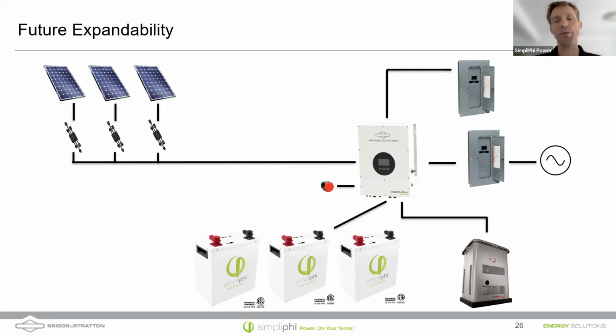The other nice thing about having that generator is generators typically operate at their highest efficiency when they're mostly loaded. So around 90% load, the generator is producing energy most efficiently from the fuel it's using. If you load that generator and supply all the loads to your house while also charging the battery, you're able to shut that generator off more quickly. So even in an off-grid setting, having batteries allows you to get more energy out of the same amount of fuel from your generator.